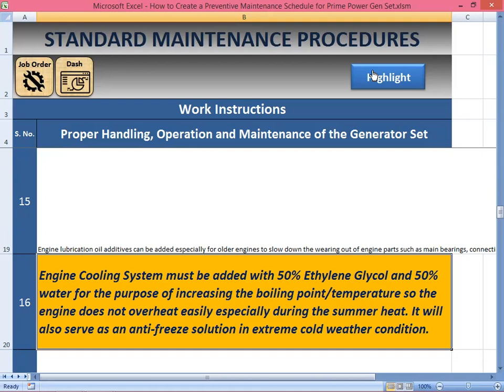Why not 100% water? To avoid rust and corrosion. Ethylene glycol helps prevent rust and corrosion, but 100% ethylene glycol is not good either, because it will eat up some components, especially aluminum parts or cast iron metal. This is bad for the metal.